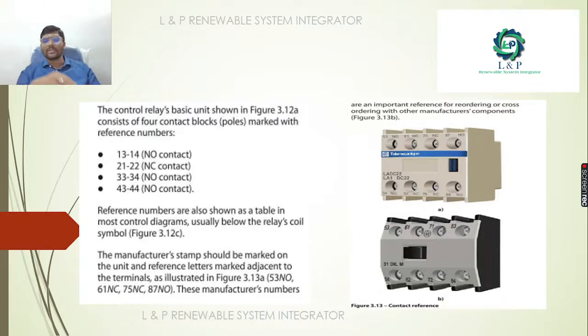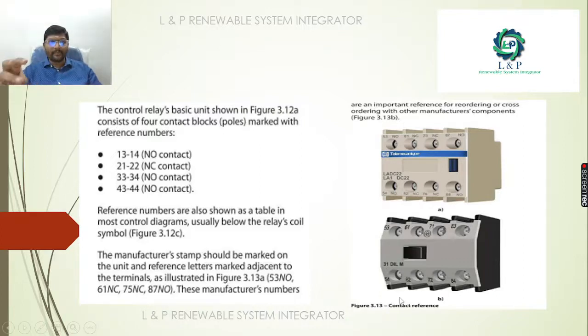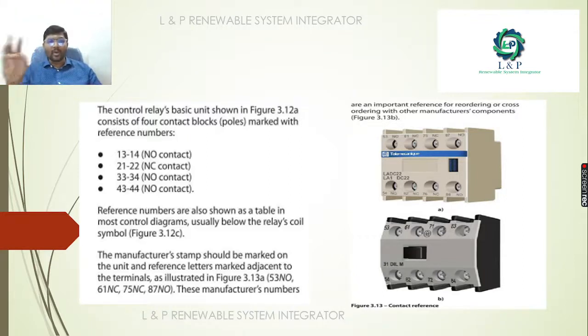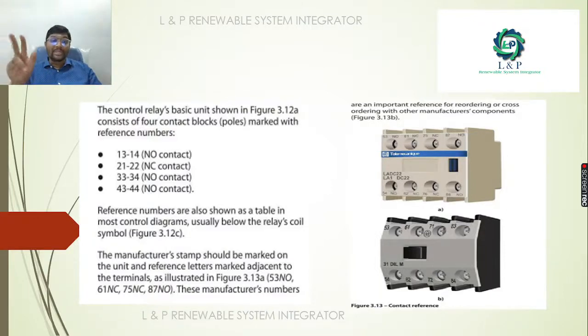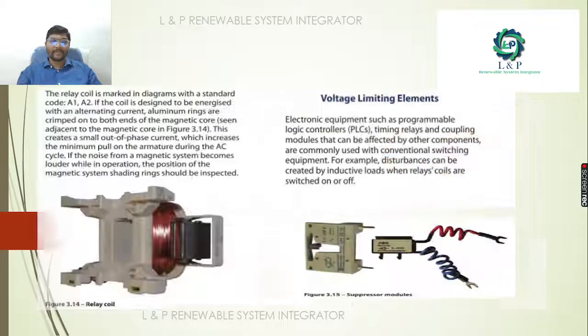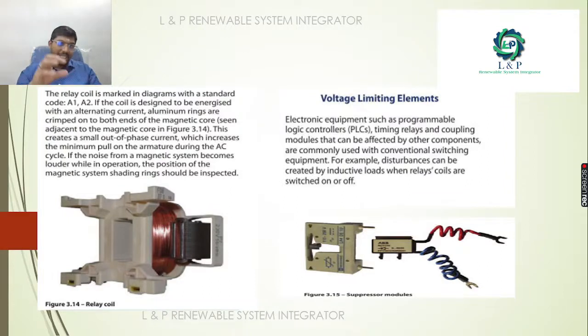Here is an example of contact reference. We have terminals 13, 14, 21, 22, 33, 34, 43, 44. Contacts 13/14, 33/34, and 43/44 are normally open contacts, whereas 21/22 is a normally closed contact. This is how a relay coil looks like — a standard code with terminals A1 and A2. There are many varieties available in the market. This coil is designed to be energized with alternating current.